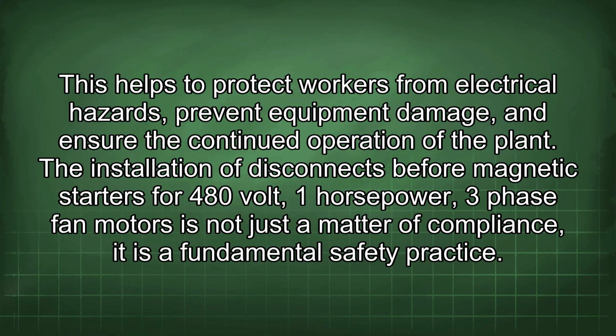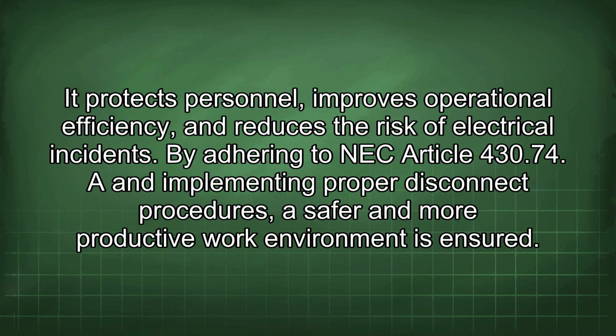the plant. The installation of disconnects before magnetic starters for 480 volt, 1 horsepower, 3-phase fan motors is not just a matter of compliance, it is a fundamental safety practice. It protects personnel, improves operational efficiency, and reduces the risk of electrical incidents. By adhering to NEC Article 430.74, and implementing proper disconnect procedures, a safer and more productive work environment is ensured.